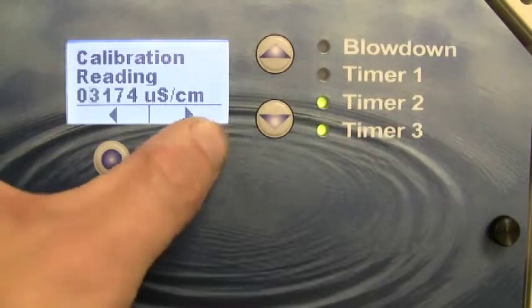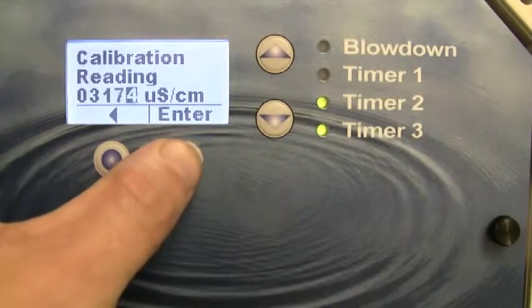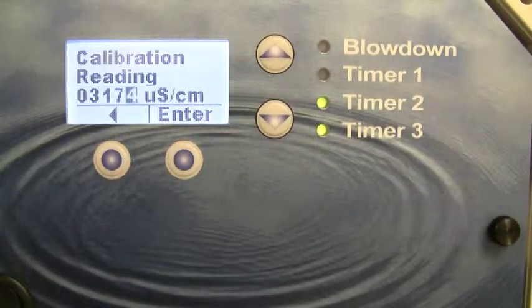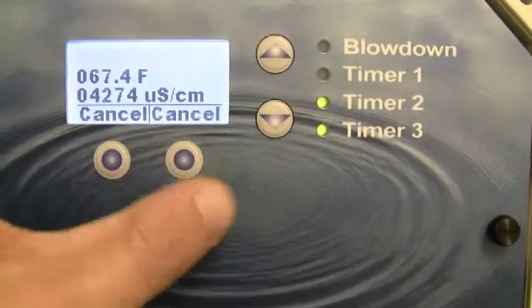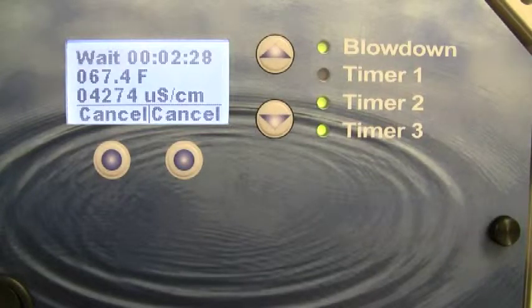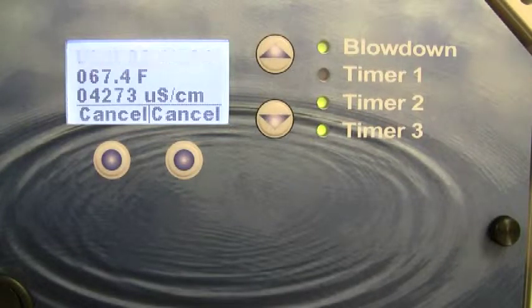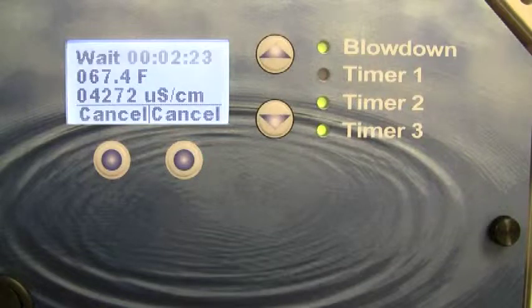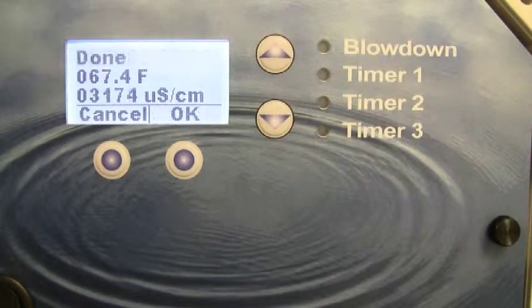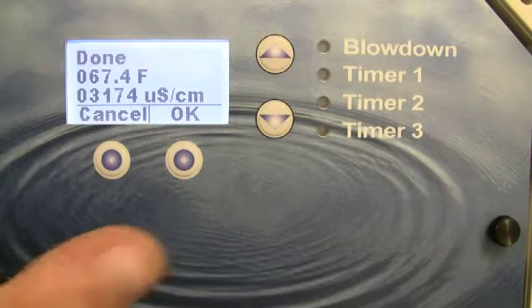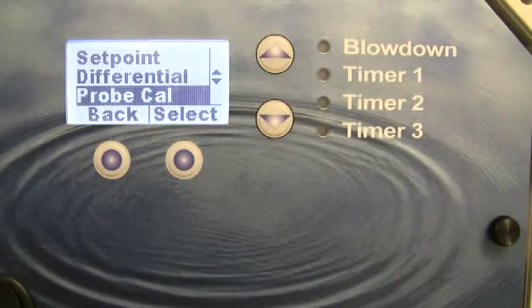Use the arrow button to move over to the next position. Change the values as necessary with the up and down arrow keys, and then press enter, and then OK. The controller will automatically begin a sample time and ask you to wait until it completes that sample time. At the end of the sample time, the controller will lock in the calibration value. Once it is done with the calibration, simply press the OK key and then press the back key as necessary to get to the main menu.